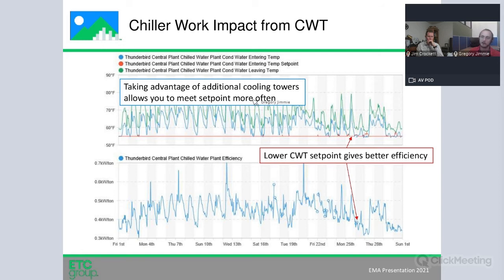One thing to note here is that when you're doing a design, or if you've already got your chiller plant built out, if you have the opportunity to take advantage of additional cooling towers, basically you have a headered system, you have some redundancies built in place, it's definitely worth considering taking extra towers in. So basically N+1 or N+2 towers to chillers. Same sort of concept is that you're running more tower fans, paying that fan penalty to offset the cost of the energy consumed by the compressor. There's obviously an inflection point where, with diminishing returns, that trade-off isn't necessarily worthwhile. So I wouldn't say 5 cooling towers to 1 chiller or anything crazy like that. But usually N+1 is a pretty worthwhile trade-off.